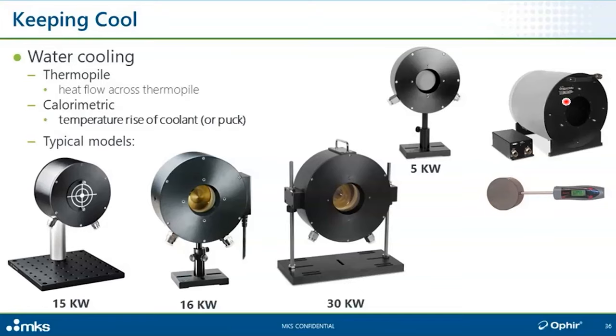Here we're measuring two things. We're measuring the temperature rise of the cooling water, and we're measuring the flow rate of the cooling water. Those two pieces of information together enable the instrument to figure out the power of the beam. The user doesn't have to worry about the calculation.